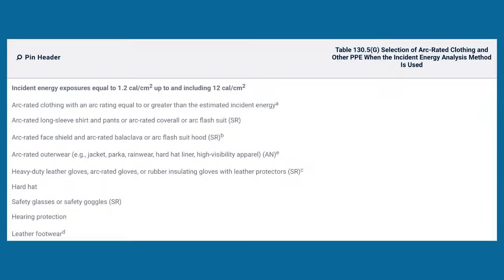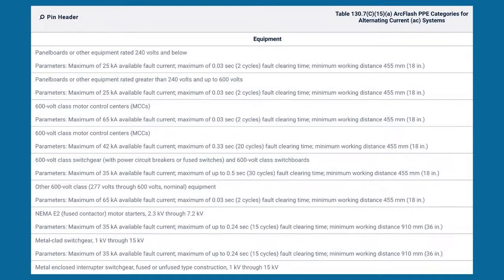When you get back here, you start looking at this. It says an arc-rated face shield. This is when you're doing it based on the calculated method. Okay. Now we're going to look a little different when we get into the hazard risk category. But here, if you do the calculation method, once you're over 1.2 cal, you've got to have an arc-rated face shield. Okay, gotcha. Okay? All right, now I'll get info. Oh yeah, that's why we do this. All right. Now, yeah, once you're in the arc flash boundary, your exposure, you got to suit up. That's correct. Now, this is where you get into the arc flash PPE categories.